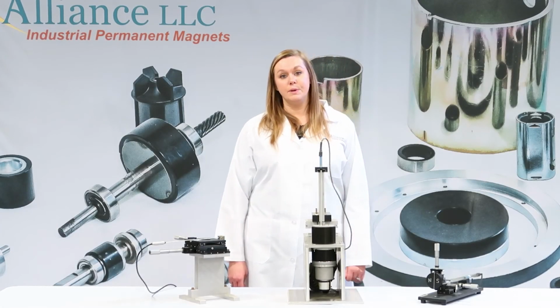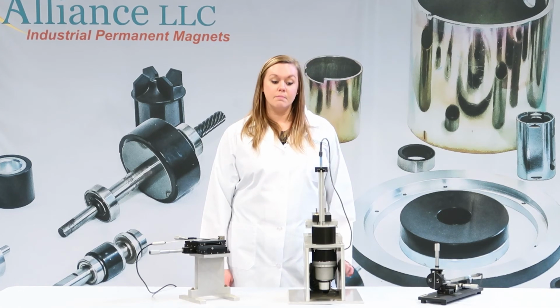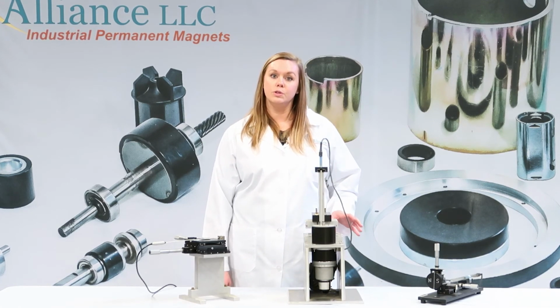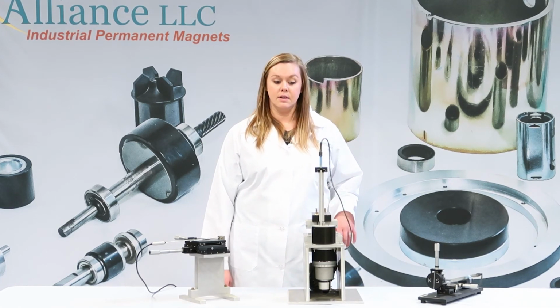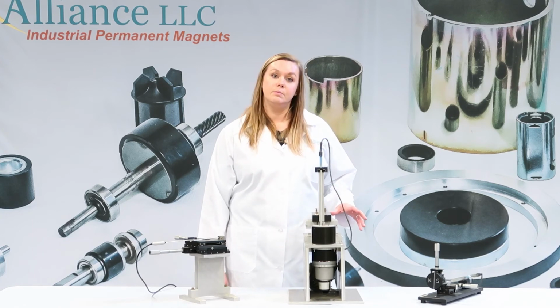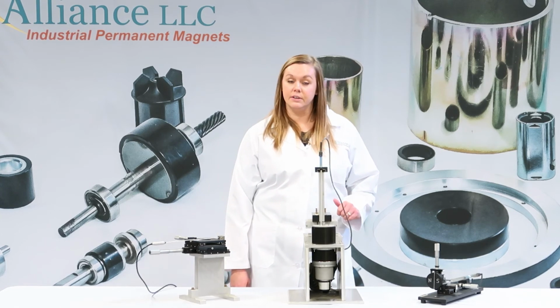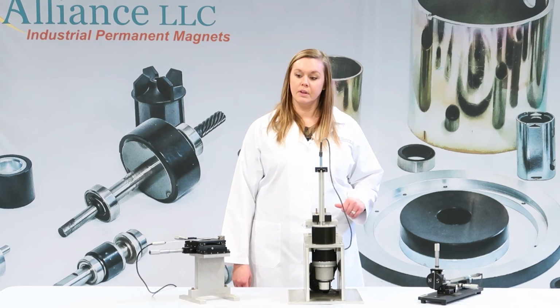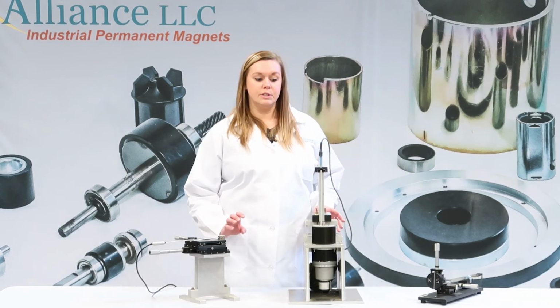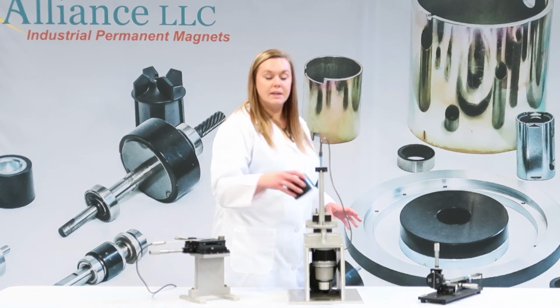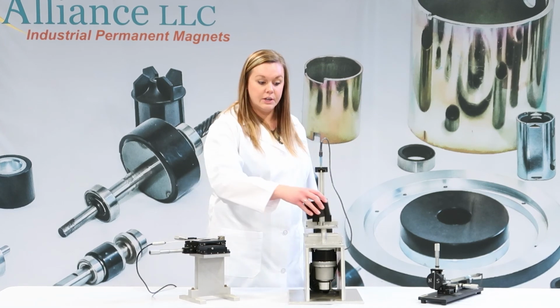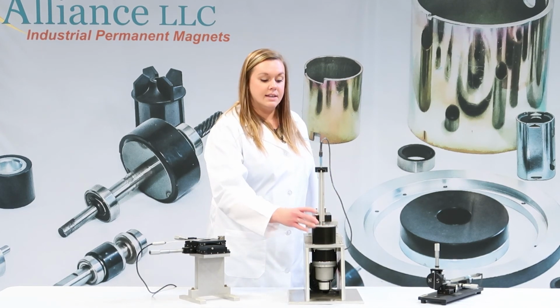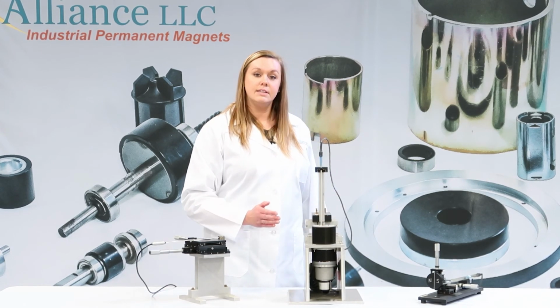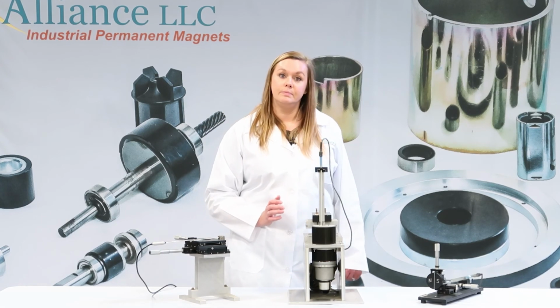Regardless of the type of Gaussmeter and probe that you choose, it is recommended to build a fixture to hold your probe and magnet into place. The fixture needs to be made of a non-magnetic material, such as brass or aluminum. The fixtures are able to ensure that when you are swapping the same type of magnet out and you're testing many of them, that it is in the same place every time and you can get repeatable results.